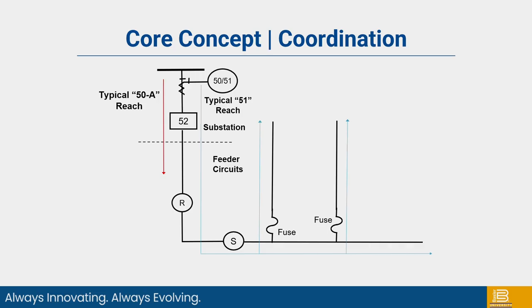So here's a one-line diagram showing a 50 and 51 with a 3-phase set of CTs going into a relay with a substation breaker with feeder circuits downstream of it. You'll notice there's fuses there because the fuses are there to isolate a smaller part of the system to minimize the area of the fault. If that doesn't clear the fault, or it's upstream of those fuses, the main breaker will open to isolate a larger portion of the system to clear the fault.